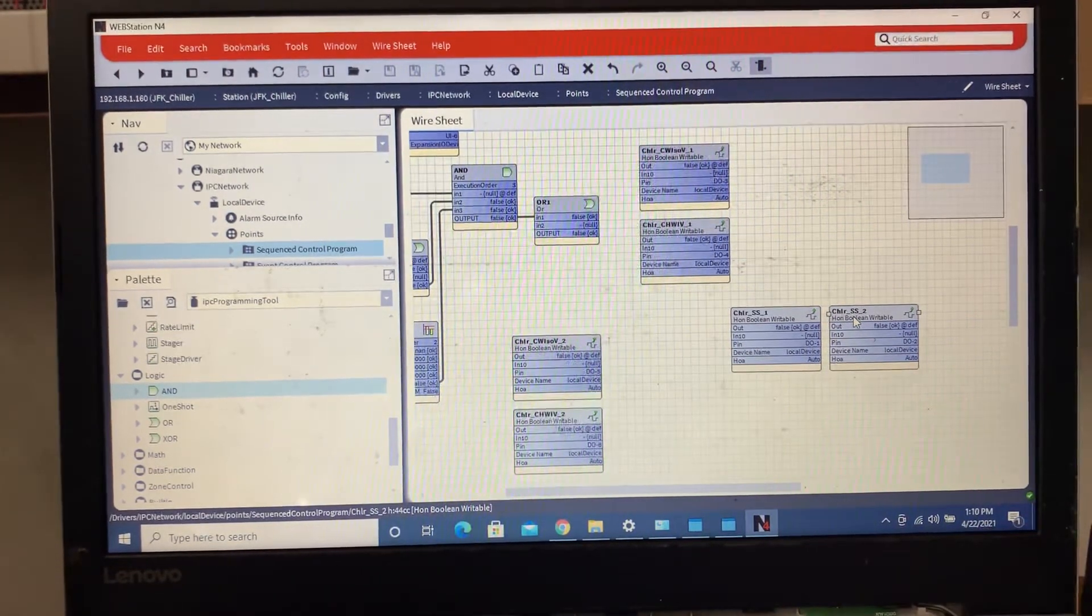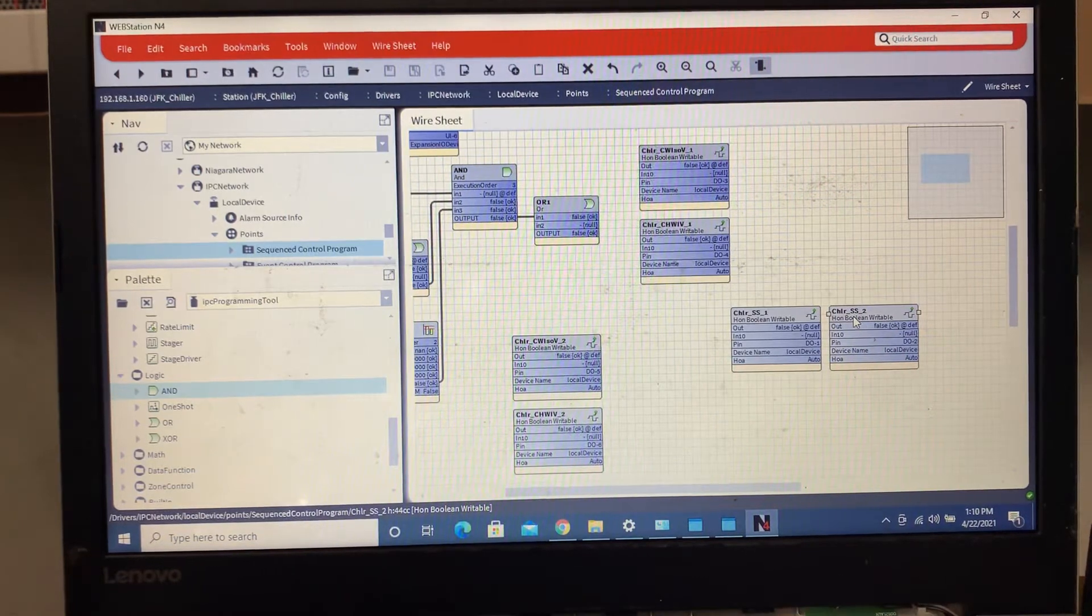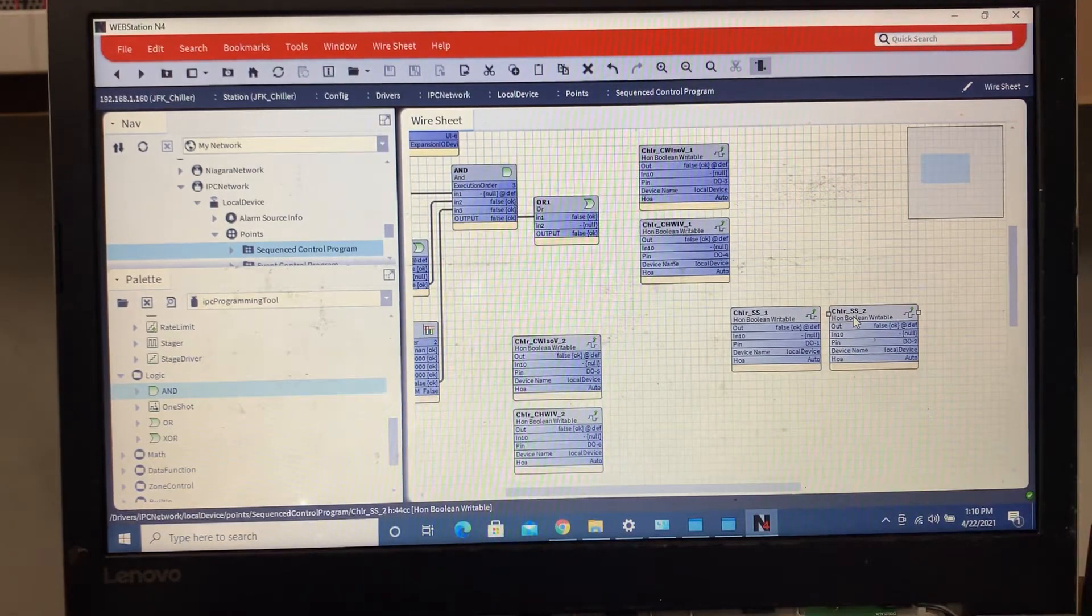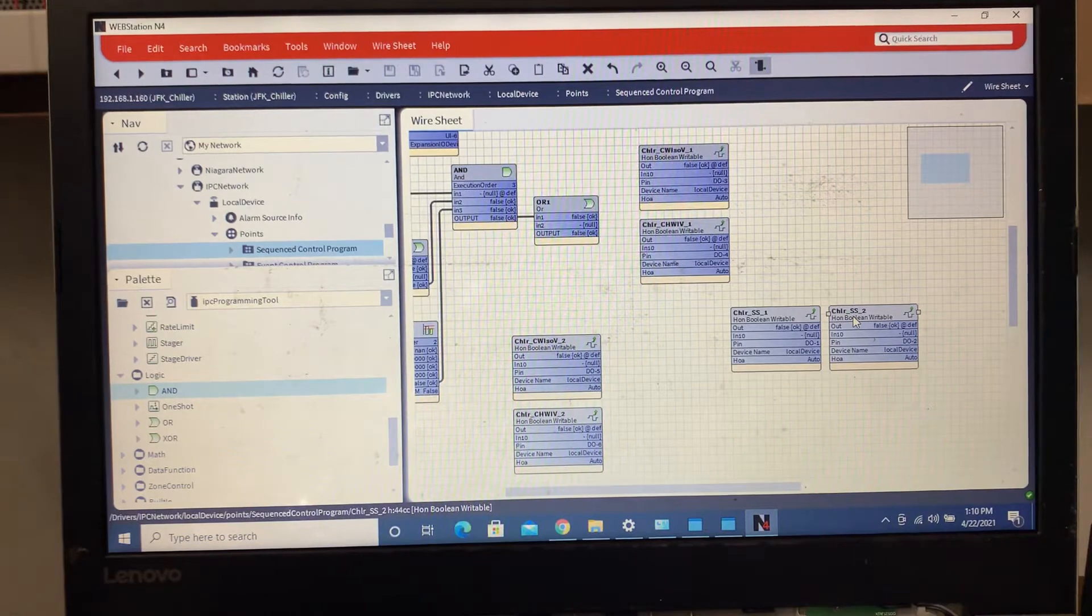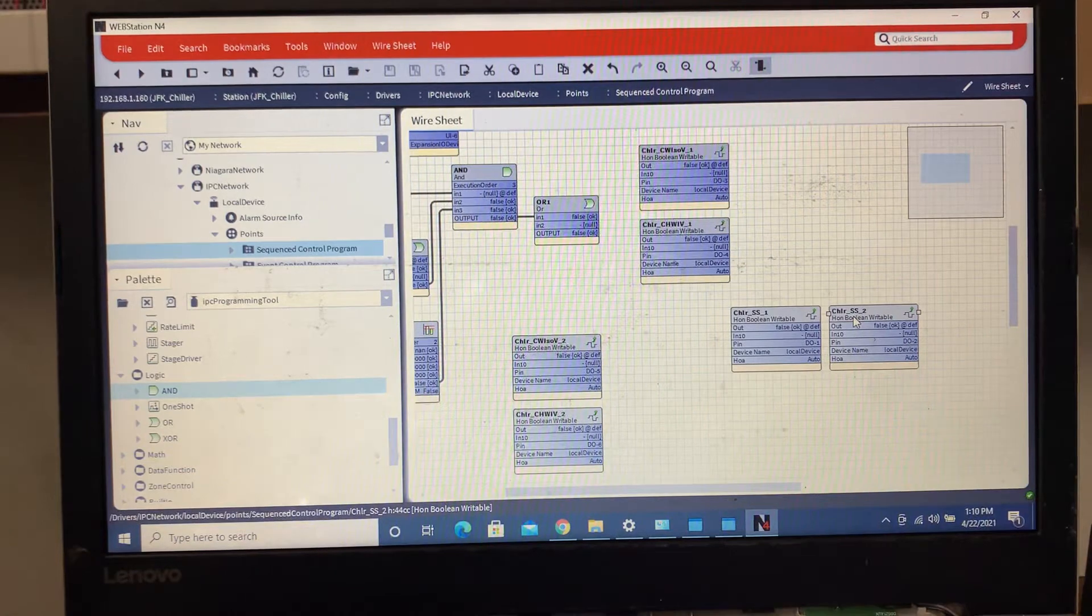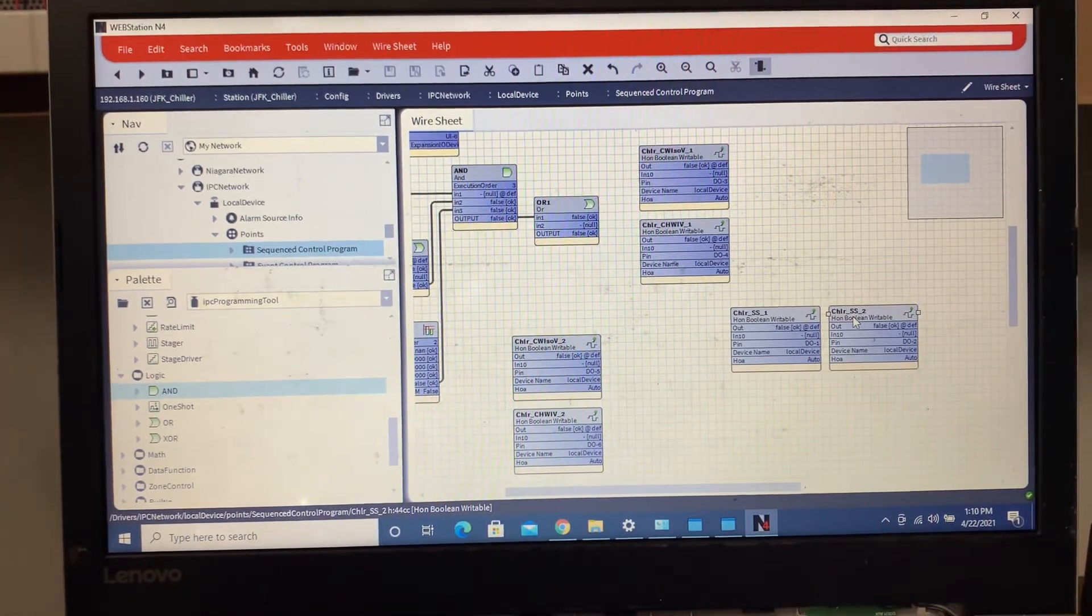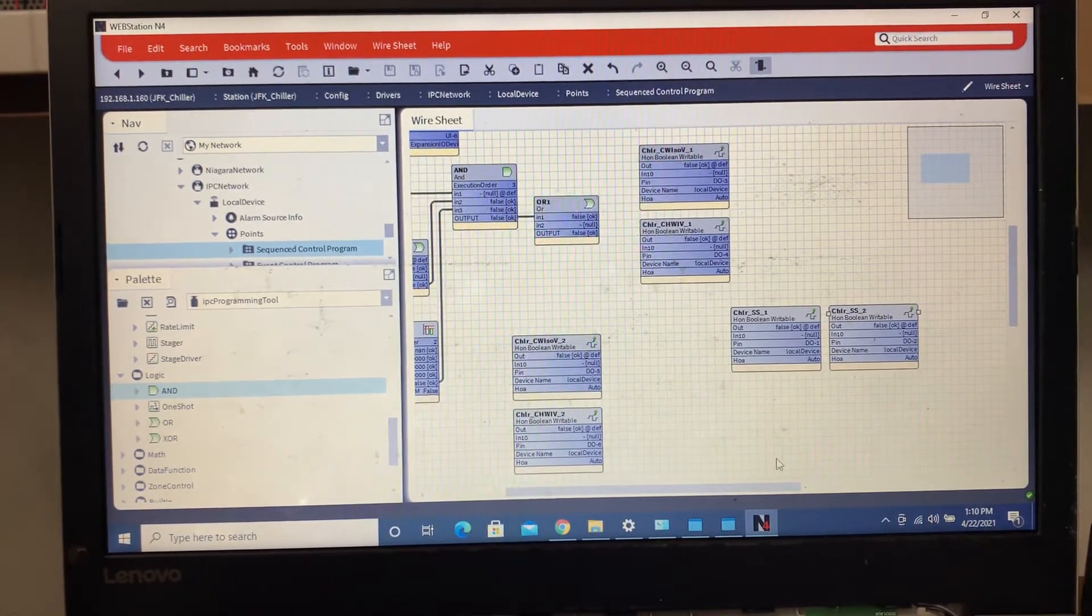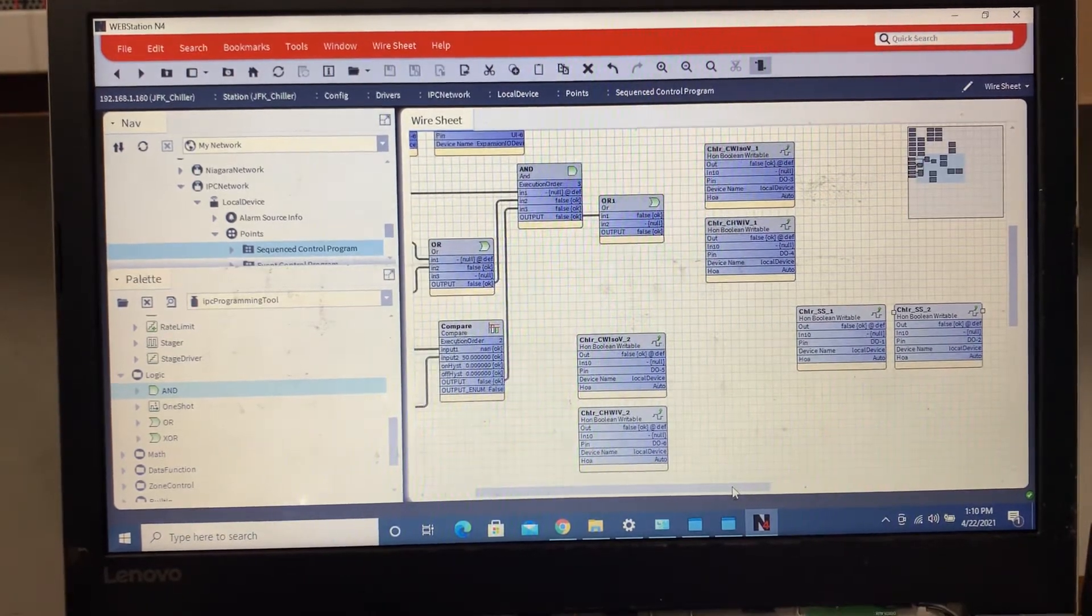Obviously with those types of chillers you want two chillers running at you know 30 to 40 percent capacity, which is going to use way less electricity versus a chiller running at 80 to 100 percent. So it just really all depends on the logic and how the sequence was written up from the previous engineer.